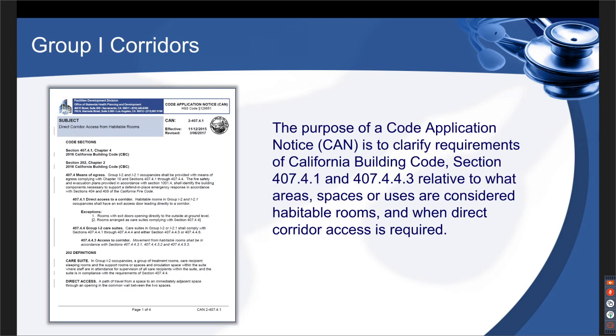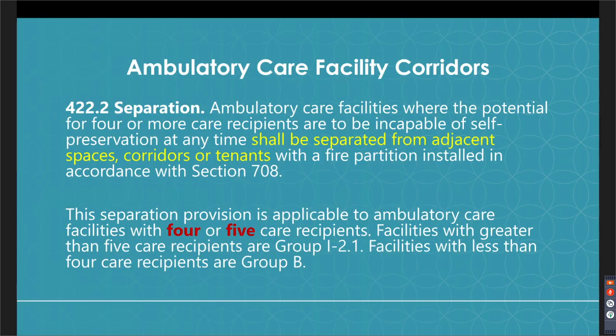Again, look at the code application notice. For this definition explanation, it goes into more detail of what areas OSHPD looks at as habitable versus not, because the definitions, NFPA 101 has definitions and we have it in the building code, and it gets kind of confusing. So that can help differentiate between what's considered habitable and what is not, for figuring out whether you need an exit access door directly to a corridor, or whether you're okay not having one in a specific space.